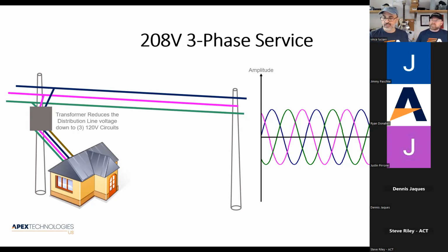It's just 3 different 120 volt circuits. The reason why it's 208 is, well, first of all, if you're using just one of those phases, it's that same 120 volts that you're getting on that split phase 240 volts, for example. But if you go between any 2 phases, instead of going from a peak on one phase to a valley on the other phase, you've got a peak on one phase and you're not quite going to the valley. So the value is 208 volts rather than 240 volts, really. And that's really the only difference between 240 volt split phase and 208 volt service. It just kind of depends on what the raw service is out there that's available to you.